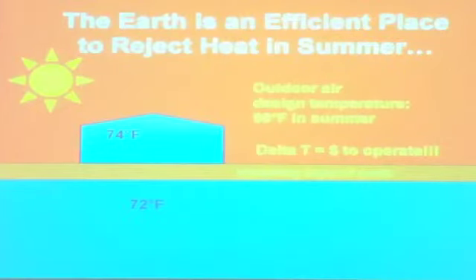Any particular soils that you prefer? No, not really. The higher the density of the soil, the better it transfers heat, but the more it costs to drill. So typically, from a capital standpoint, it's about the same cost per ton if you wanted to use ton as a metric. Can you use the rule of thumb of one well per ton? You can use that. That's a metric that a lot of people understand. There's more to the equation, but that's a good rule of thumb.